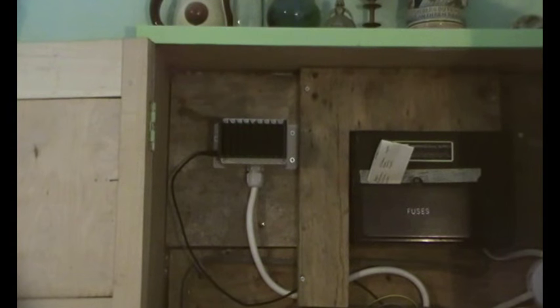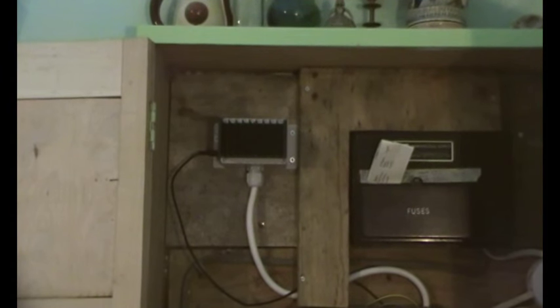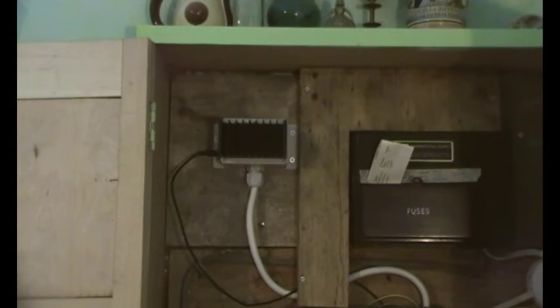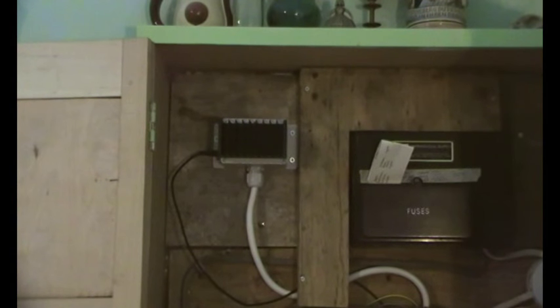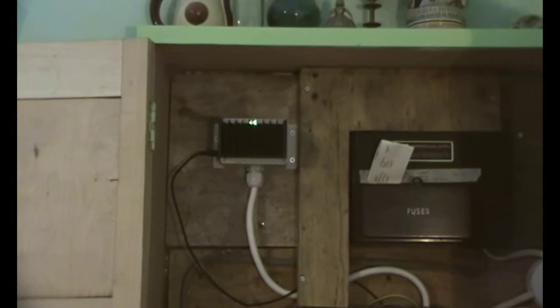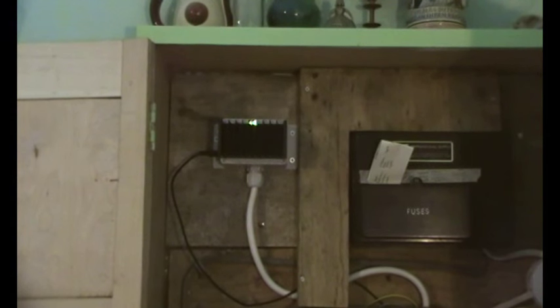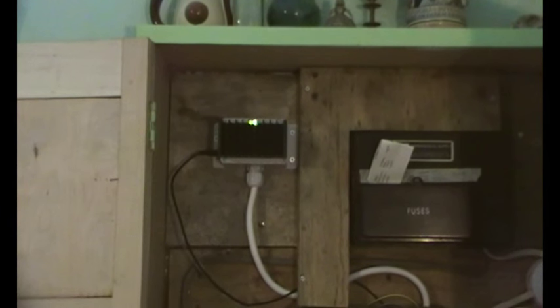So according to the book, if you're installing after dark, well it's light but the panels are in shade now. So it says if you're installing after dark there is no solar energy available, you would expect the LED to flash once per second, on for half a second then off for half a second, indicating energy import.